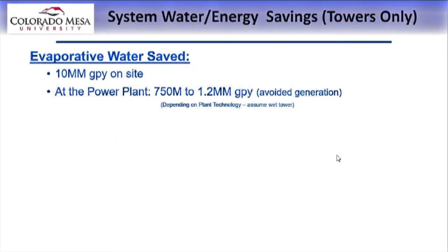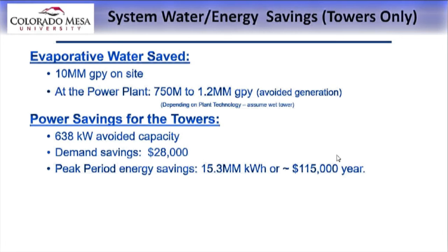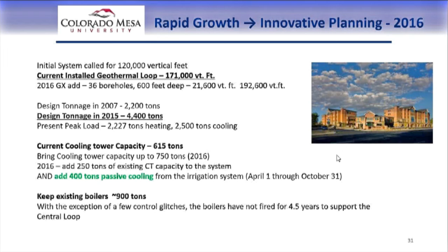So here's what evaporative water, power savings, and capacity look like. That's just the hypothetical annual savings for about a 2,500 total hour runtime. And as you well know, in a well-controlled system that might be fine, but in a poorly controlled system it's probably double that. But that's just on the tower use. And just general statistics: design tonnage now 4,400 tons, we've got 2,200 connected, tower capacity up to 750, and we've kept the boilers that we're not using.